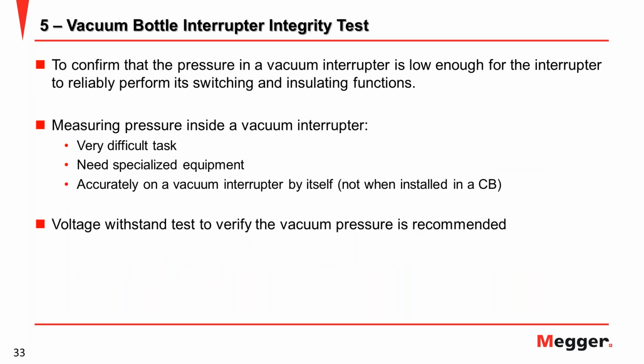Okay, next I continue to the additional test, especially for vacuum bottle breakers. The purpose of the vacuum integrity test is to confirm that the pressure in the vacuum interrupter is low enough for the interrupter to reliably perform its switching and insulating function. Normally we need to measure the pressure inside the vacuum interrupter. But the problem is that it is a very difficult task, needs special equipment, and must be done on the vacuum interrupter by itself, not when installed in the CB.